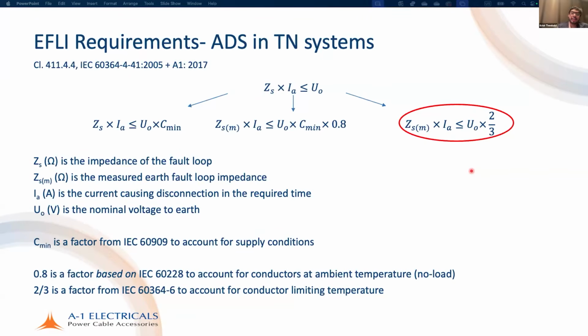When we want to disconnect, there is a very crucial requirement for automatic disconnection of supply. This is the earth fault loop impedance. The earth fault loop impedance shall be less than or equal to U0 divided by Ia. So this needs to be kept to a minimum. In India, we also add a further 2/3 safety factor.